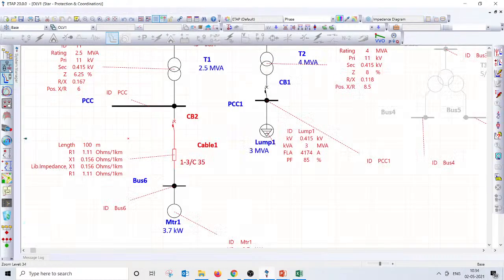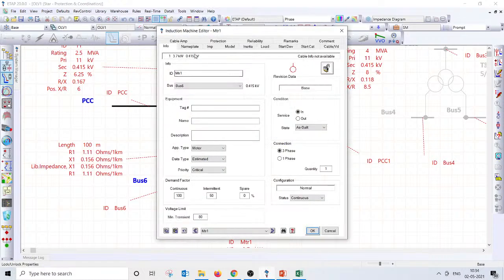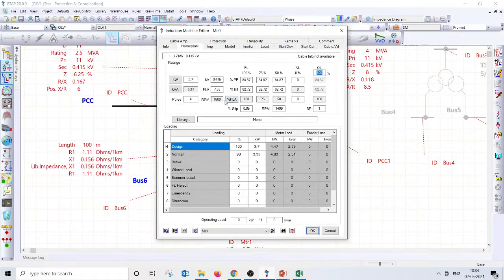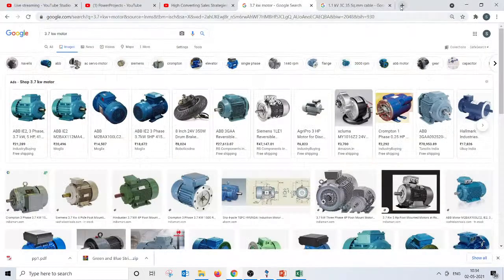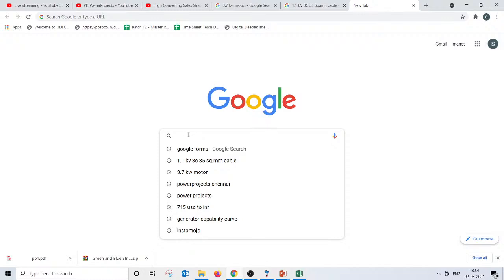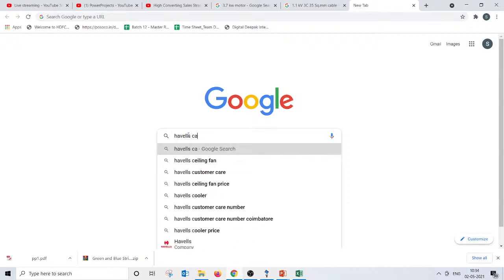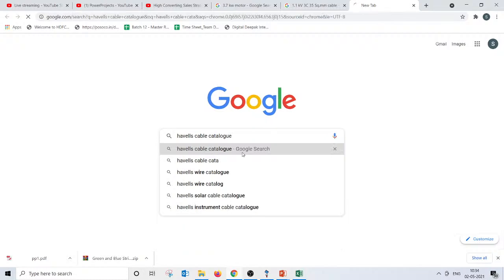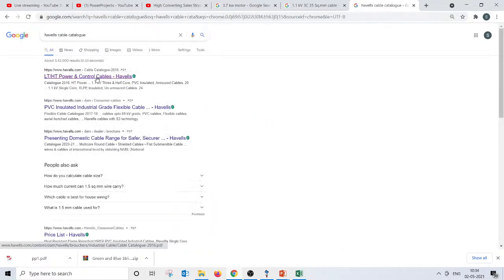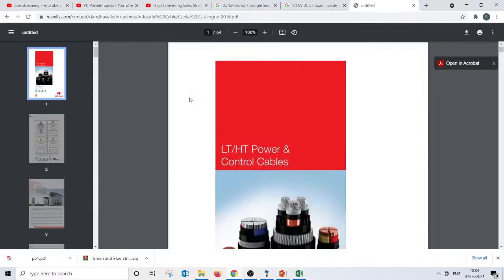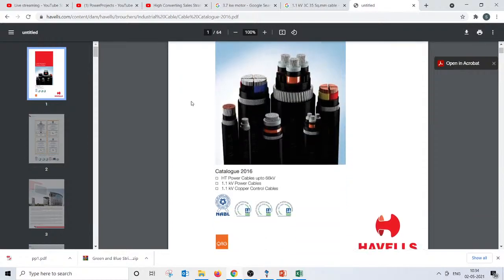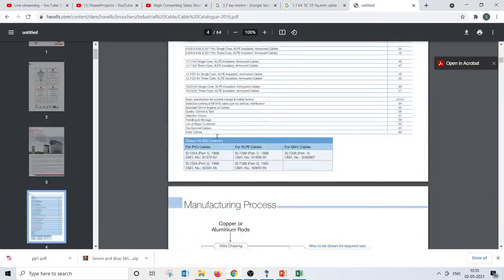Here the cable which I have selected is heavily oversized. How can I claim that? The full load current of 7 amps can be easily carried even by a 2.5 square cable. If you're in doubt, you can find some catalogs. I'm just putting Havells. You can use whoever is your favorite manufacturer; I have used Havells quite a few times. At least the catalog is great.